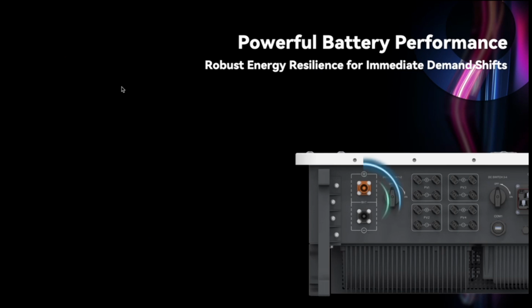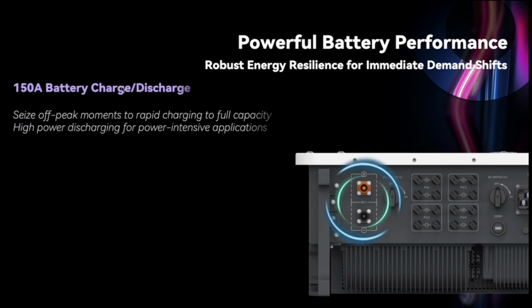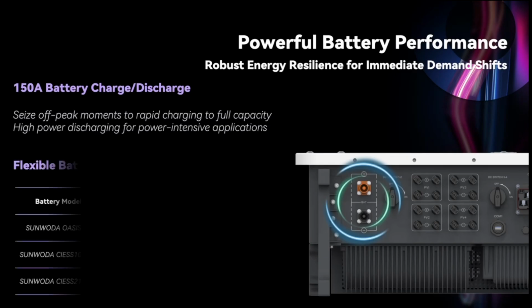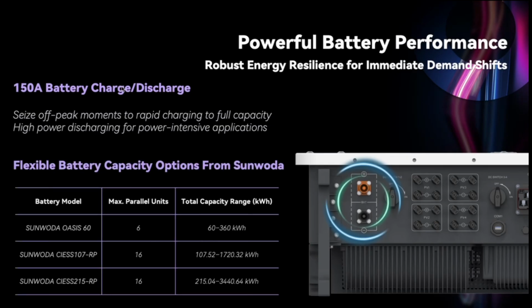And now let's take a look at the battery's performance. So this inverter is equipped with a dedicated battery input, and it supports up to 150 ampere charge and discharge current, which means faster charging during the off-peak hours and a stronger power output for the energy-intensive applications. And when it comes to the battery options, we collaborate closely with Sunwoda, offering flexible capacity combinations.